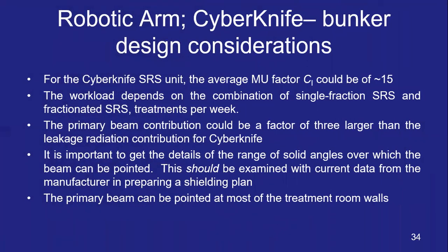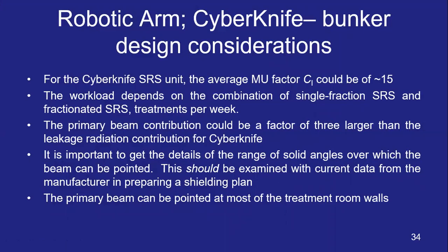For the CyberKnife robotic SRS unit, the average MU factor C1 can be as high as 15. Workload depends on both single fraction and fractionated SRS treatments, so weekly workload calculation should include both. The primary beam contribution can be a factor of three larger than the leakage radiation contribution for CyberKnife. An important consideration is obtaining the range of solid angles over which the beam can be pointed from the manufacturer, as the primary beam can be directed at most treatment room walls, making most walls primary barriers.